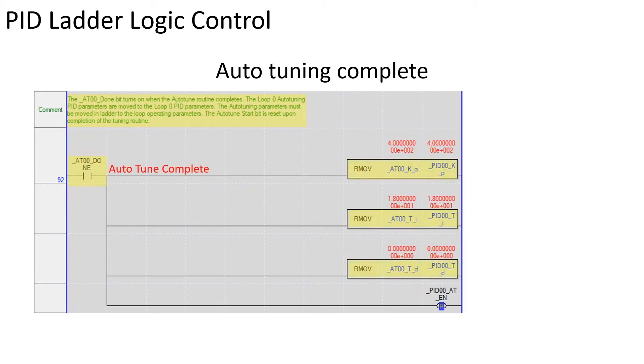In rung 92, when the auto-tuning routine completes, the auto-tune variables are moved to the PID operational variables for loop 0 in a real number format. The PID auto-tune enable bit is also reset.